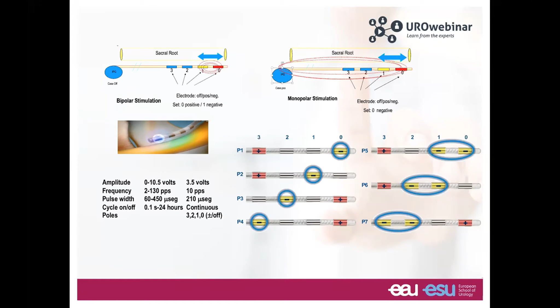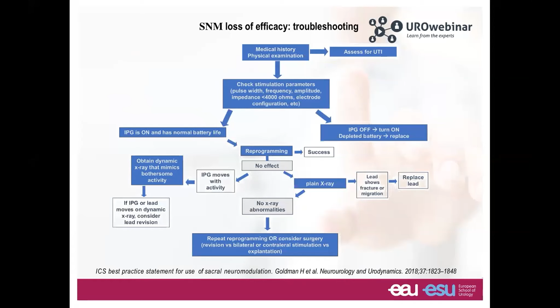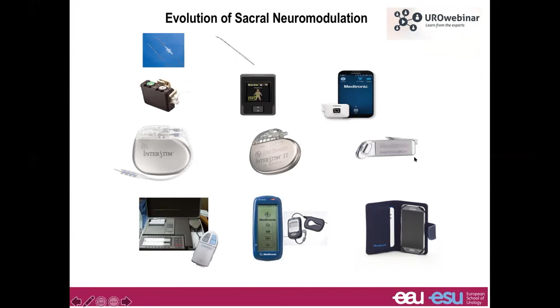The International Continence Society has provided a recommendation for troubleshooting of the device with this algorithm, taking into account whether or not the patient has enough battery length or has high impedances, and using X-ray and with a proper clinical approach, we can handle most of the patient problems. But sacral neuromodulation has been in continuous evolution. As I mentioned, initially we used a short electrode that had to be implanted openly. Now we use the tined lead, but the system has evolved rapidly. Now we have a smaller device, a smarter programmer, and even an MRI compatible device and electrode, which will allow many more patients to benefit from the therapy.